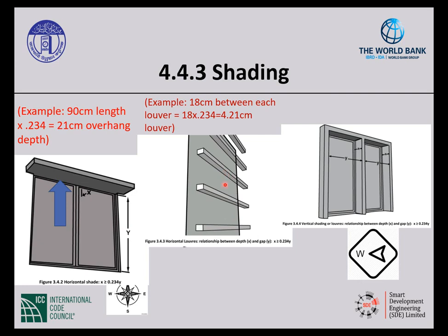All right, so you have those two options on south, east, and west: a horizontal projection or these horizontal louvers. But then it goes even further to say that if you have windows on the west, you also have to provide vertical shading, vertical fins. So vertical shading devices shall be provided on the west, the depth of which shall be calculated by multiplying the gaps in between by the 0.234. For example, if we had 90 centimeters between these fins, we'd take that 90 times the 0.234, and we'd get that these fins have to be at least 21 centimeters in depth. So this is on the west. You can see that on the south, east, and west, we have to do something horizontal. But on the west, we also have to do something vertical.